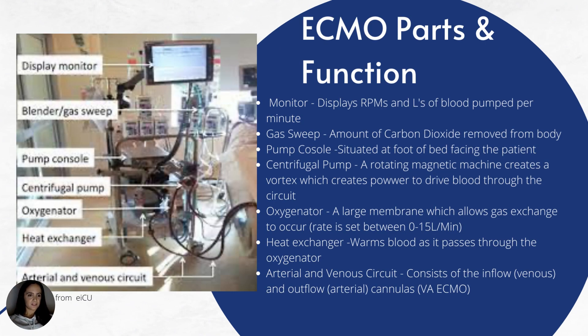The ECMO circuit has several key components. There's the display monitor, the blender or gas sweep, the pump console, the centrifugal pump, the oxygenator or gas exchanger, and the inlet and outlet venous circuits. The monitor displays the numbers we want to see — mostly what we're writing down hourly in the patient's chart — including the patient's RPMs and liters of blood pumped per minute. The liters per minute is really important; that's what we're looking at most of the time to see if the ECMO is working accurately.